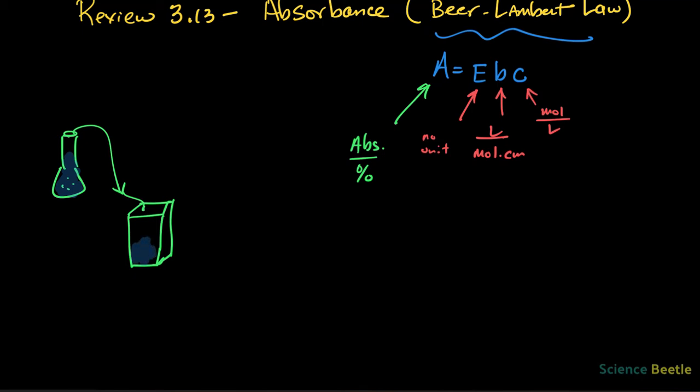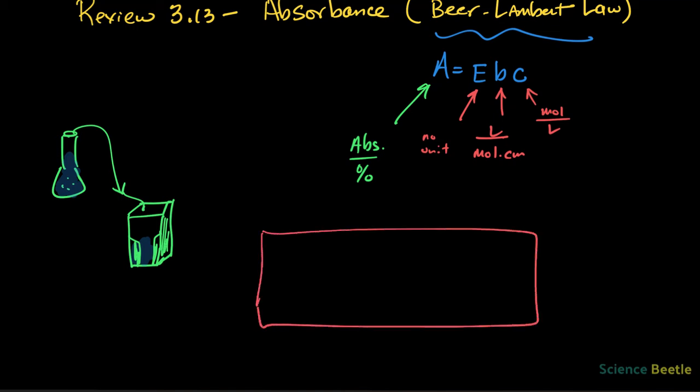And there are ridges outside on the cuvette, extensions that come inside, and light is really going to travel between these. So when we put this in, we want to arrange the cuvette in such a way that this portion right here is aligned in the machine. So the machine is, let me just draw the skeleton part here. If I make a copy, this copy here will essentially bring it in, and let's do it this way.